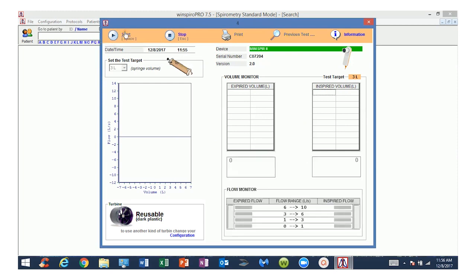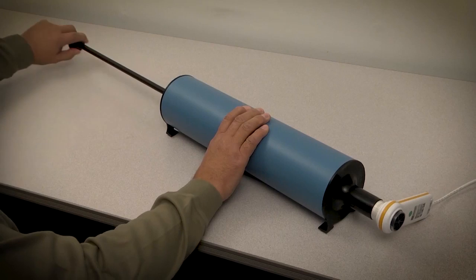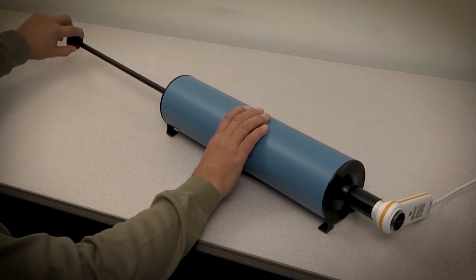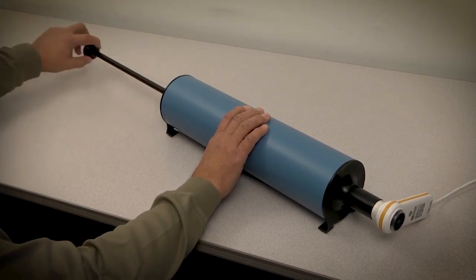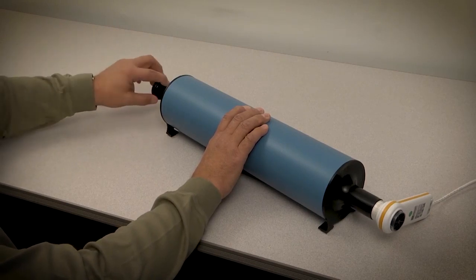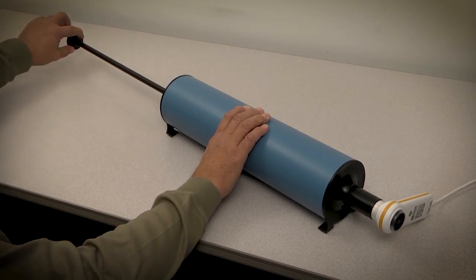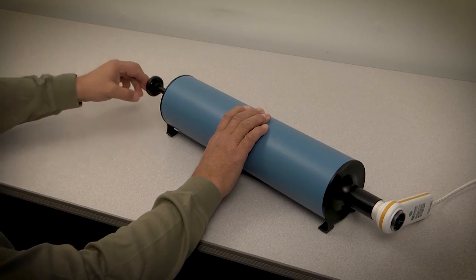Always check to be sure that you have a tight seal and that no air is leaking at the syringe or the turbine. If the results are still outside of the 3% range again, redo the test for a third time, again checking to be sure you have a tight seal and that no air is leaking at the syringe or the turbine. And be sure to pull and push the syringe piston all the way to the built-in stops in each direction. If you do not get a passing range of plus or minus 3%, contact MIR customer support.